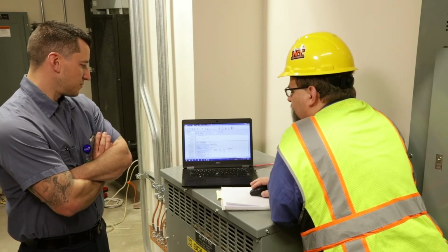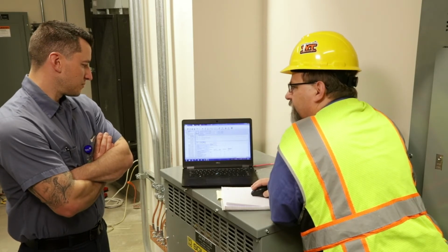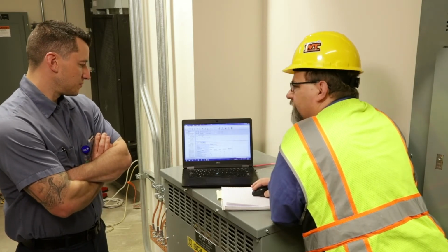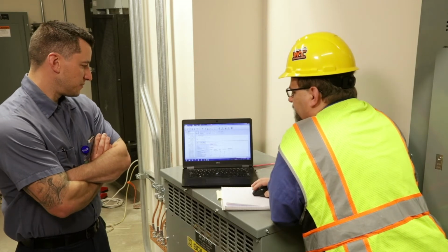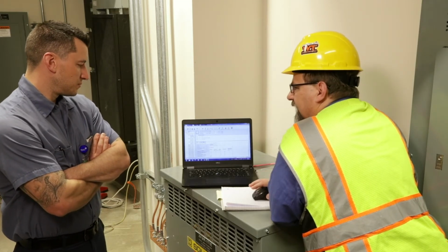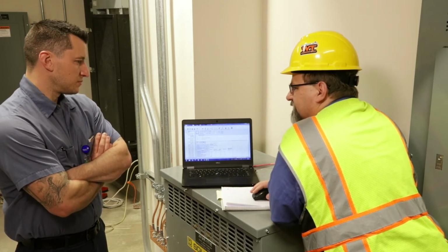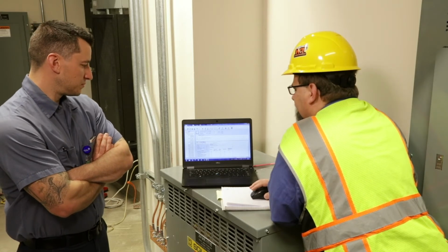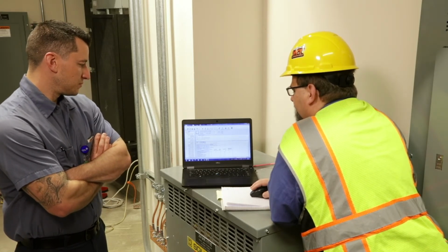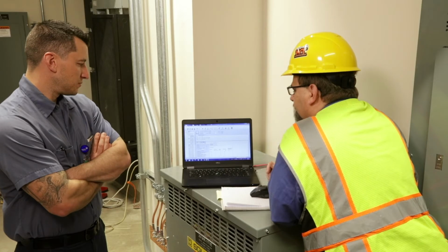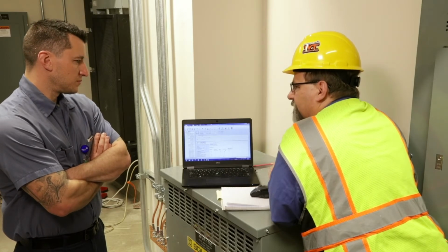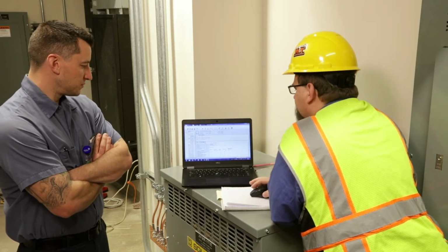You can see what you have to program. There are different trim levels, like it can go from 0 to 100 if we wanted to limit it to only go to 80% and only go down to 15%. Sometimes you get a light and it's just flickery at 10% and you want to change the way it's done, then that's the kind of thing you do here. Again, with that infrared thing, I can tell it a minimum trim level also, right?